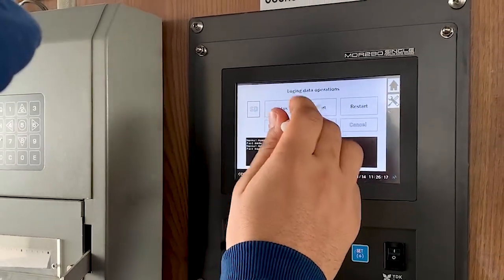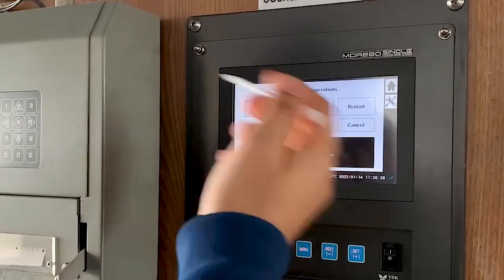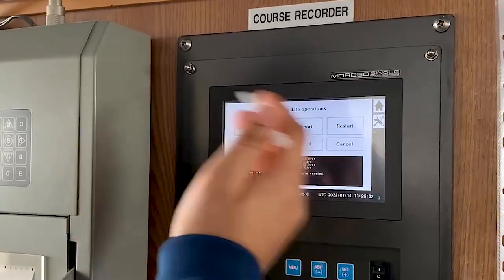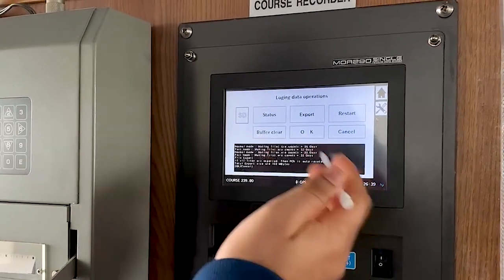If you want to export, you can click here — export. If all files are exported, then the MDR will be automatically restarted. It will export all the files to the SD card and then reset. After exporting, we have to do a buffer clear — the onboard memory should be cleared for the next 32 days. So after exporting, you press buffer clear and OK.